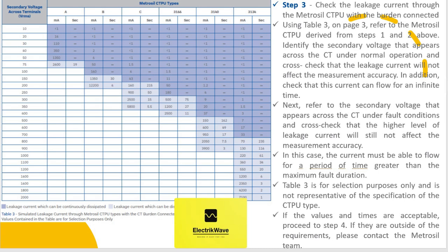Next, refer to the secondary voltage that appears across the CT under fault conditions and cross-check that the higher level of leakage current will still not affect the measurement accuracy. In this case, the current must be able to flow for a period of time greater than the maximum fault duration. Table 3 is for selection purposes only and is not representative of the specification of the CTPU type. If the values and times are acceptable, proceed to Step 4. If they are outside of the requirements, please contact the Metrosil team.